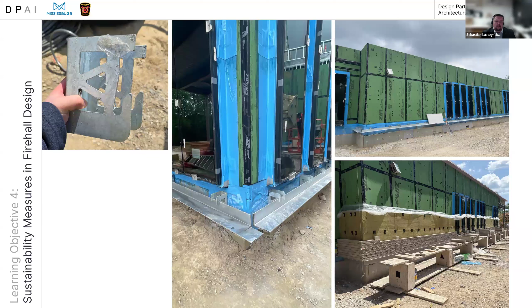Now, working our way from the exterior into the inside and the mechanical plant, we designed the building around air source heat pumps connected to a VRF fan coil system. This gave us efficiency through electric heating and cooling, with the flexibility required in a 24/7 facility. Our VRF system allowed us to zone the station, living quarters, offices, training, and support areas, so that each of those zones responds to how it's actually being used. That improved the comfort for the crews while avoiding unnecessary conditioning in low occupancy areas.